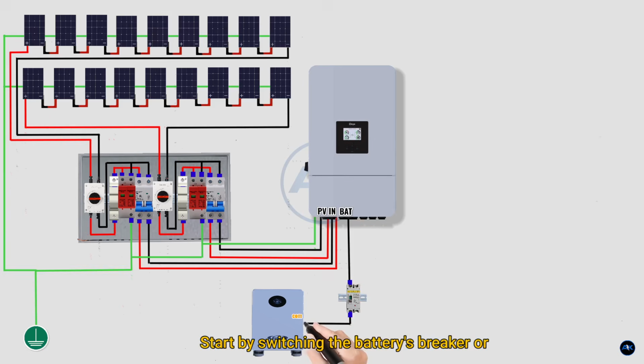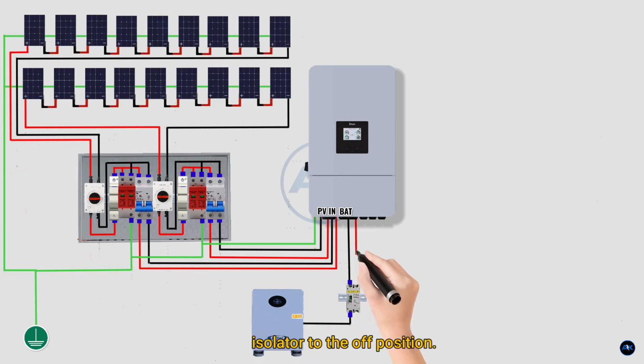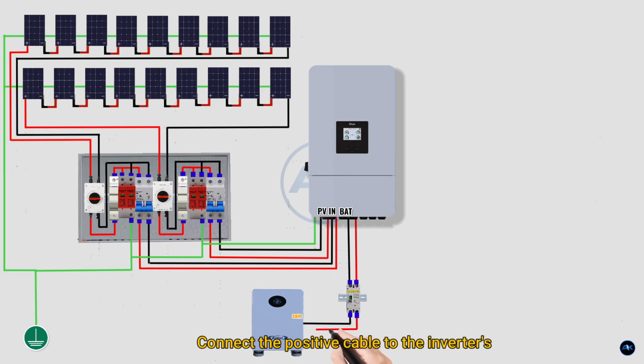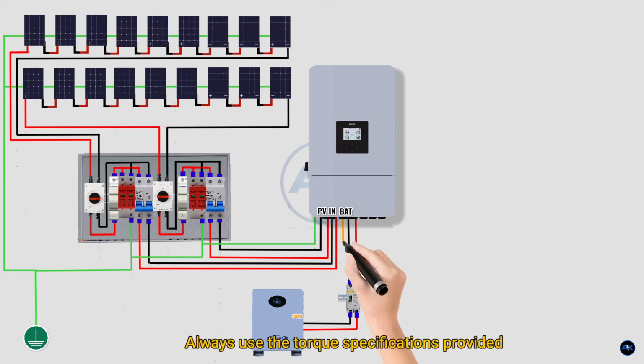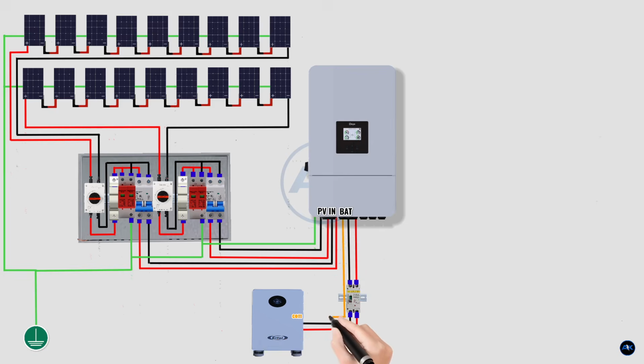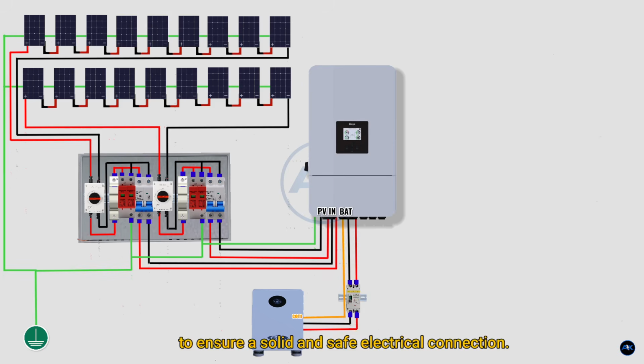Start by switching the battery's breaker or isolator to the off position. Connect the positive cable to the inverter's battery positive terminal and the negative cable to the battery negative terminal. Always use the torque specifications provided by the manufacturer to ensure a solid and safe electrical connection.